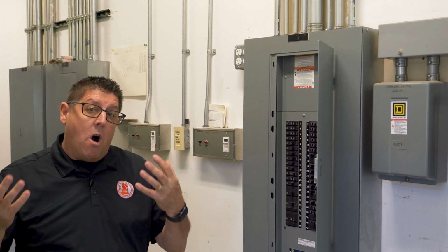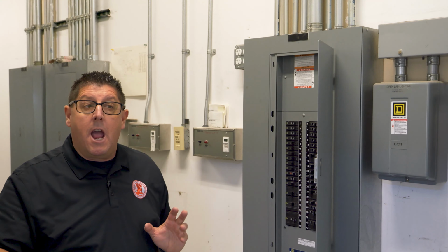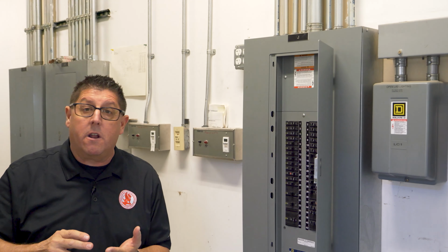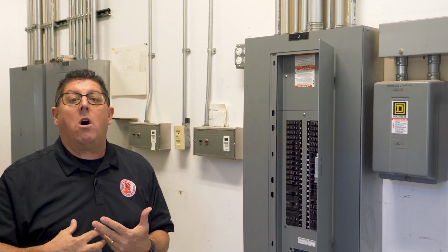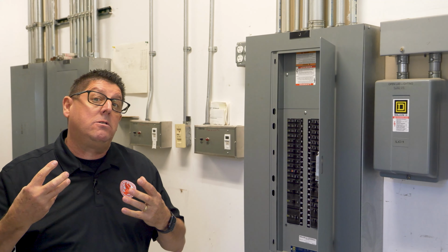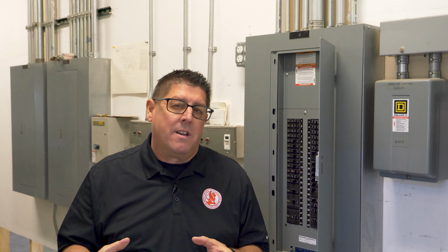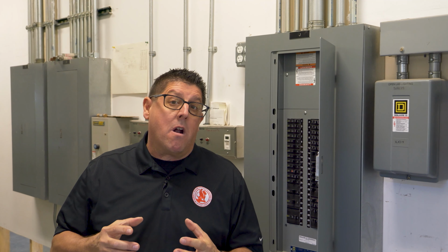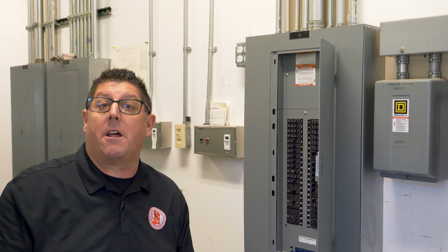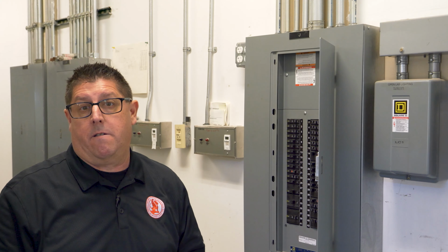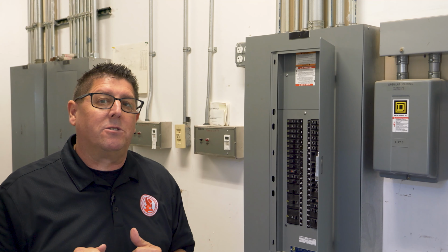Then it's important when you're all finished with your entire inspection and you've gone through and identified your 20, 30, 40, however many panels there are on your schedule, you take all of those remarks, any deficiencies you found, and then highlight those on your report software. An example of that would be, there are open knockouts or missing filler plates on panels H, H1, D2, etc. So what you do is you're assembling those remarks to make it easy for your clients to read.